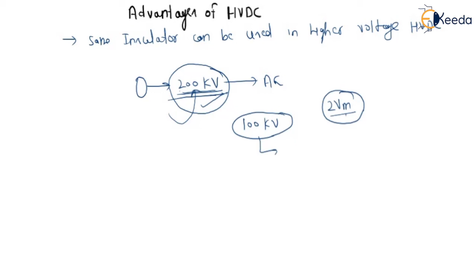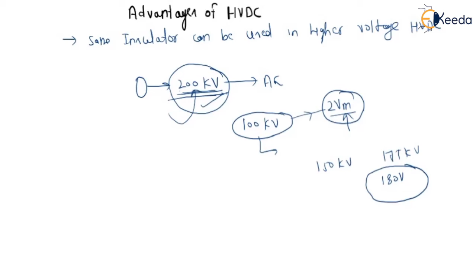If the operating voltage is 100 kV, the insulation required is 2 Vm, and we have seen this in the current chopping phenomenon. But if we use this insulator in HVDC, it can be used for at least 150 kV, or 175 kV, or 180 kV. So for higher voltage we can utilize the same single insulator. This is the basic advantage of HVDC. So this is all about the advantages of HVDC. Thank you.